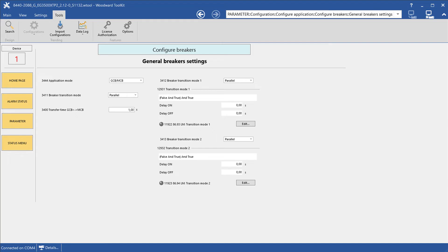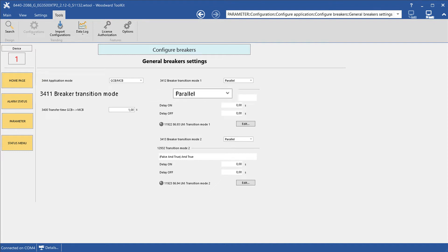First, let's look at where the transition mode can be configured in the toolkit software. You can find the breaker transition mode, parameter 3411, in the general breaker settings menu.